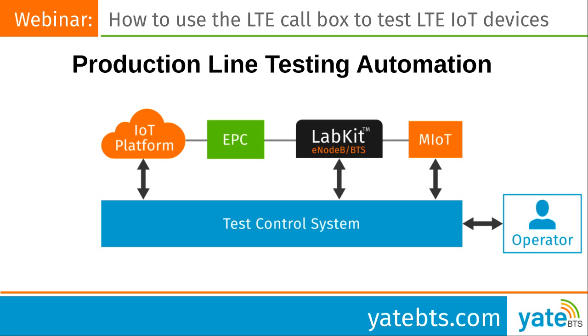And these different communication interfaces between the IoT platform and the test control system, it's probably some sort of web-based API. Between the mobile IoT device and the test control system, it's probably a serial port connection. That seems to be most common. And then between the test control system and the LabKit, it's going to be an IP connection. You actually have two options there.